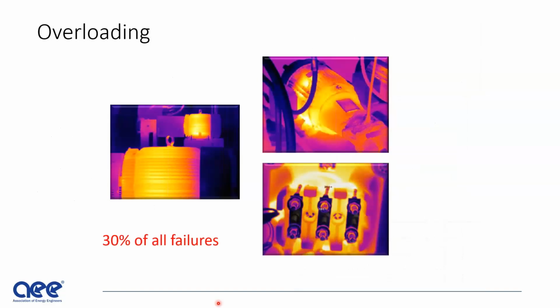Overloading: we see overloading not only from load on the shaft, but because of the 5th harmonic and poor temperature or thermal management. Here you see we used infrared imaging and we saw a plume at the power connection, which gave us the idea that this was being overloaded. We opened it up, and sure enough, if I was to show you the actual photograph, the insulation of that wire was black due to the char.